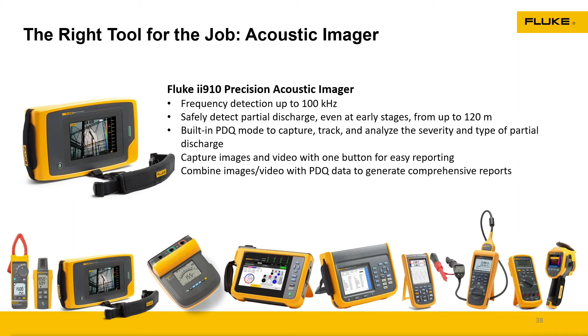So in summary, we've talked a lot about the whole system, but start right by testing right. Check for those ground faults, make sure you have the right tools for the right job. Integrate testing into your installation workflow. It's going to actually save you time and money. One component I didn't talk about was a proving unit. That's part of the NFPA 70E standard. Prove that your meters are working correctly prior to going out and doing your work. Prove that it's going to work.